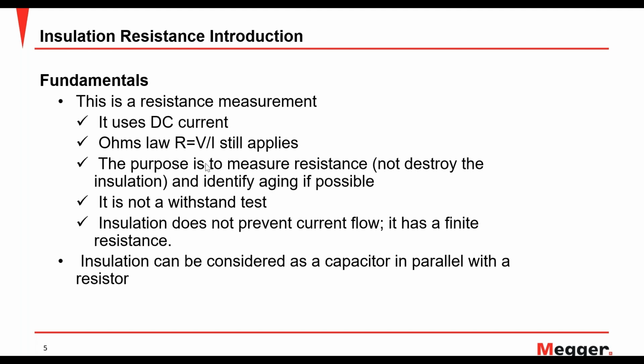So insulation resistance is basically you're using a DC current in order to measure your resistance. It's the basic principle of Ohm's law. You are keeping your voltage constant and you are measuring the leakage current, which gives you, in terms of equation, your resistance. And the main purpose is to measure the resistance and not destroy the insulation, and identify aging if possible. If you're trending results, that's when you can see how the insulation is aging or degrading over time.